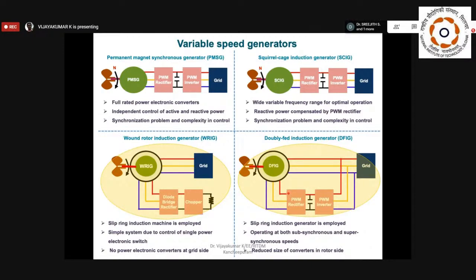When we come to the doubly fed induction generators, they use a reduced size of converters, only 30% power converter rating, because you are dealing only with the slip power. The major advantage of the doubly fed induction generator compared to the wound rotor induction generator is that you can increase the speed range.